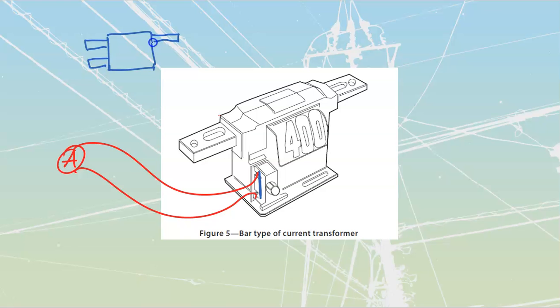When you get these, they do not have lugs bolted on - just bolt holes. You'll have to bolt lugs on using your proper torque wrench to get the correct torque. You should not be eyeballing this - professionals, act like it. Buy yourself a $12 Mastercraft torque wrench, one of the manual ones, and use it on those things because there's a lot of expansion and contraction.